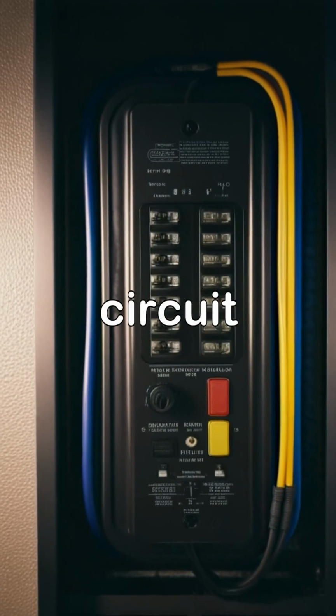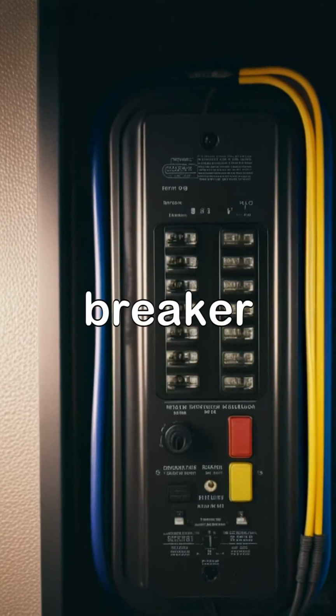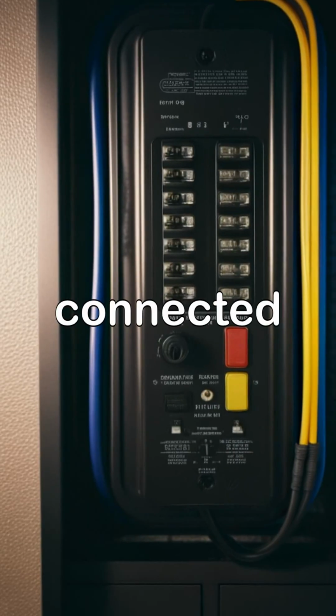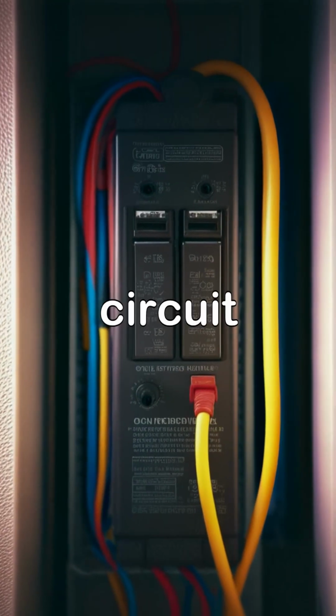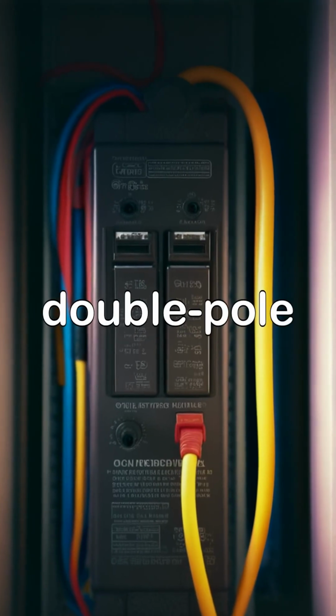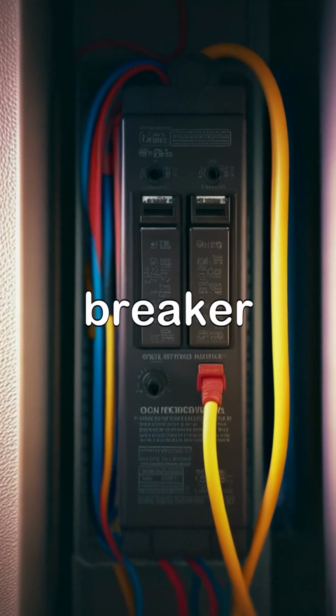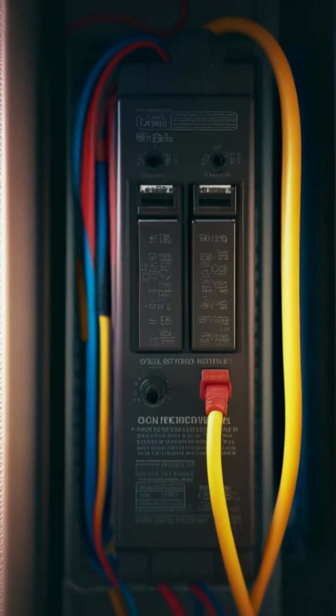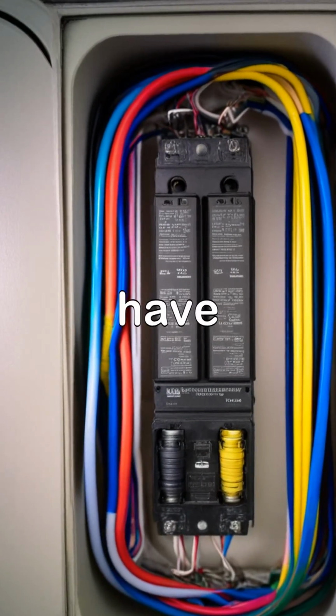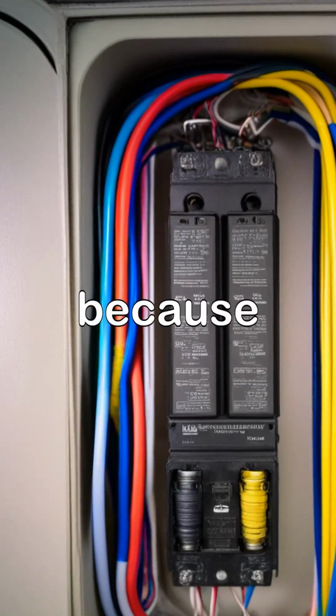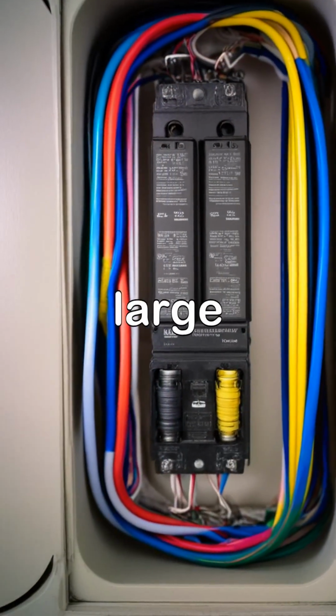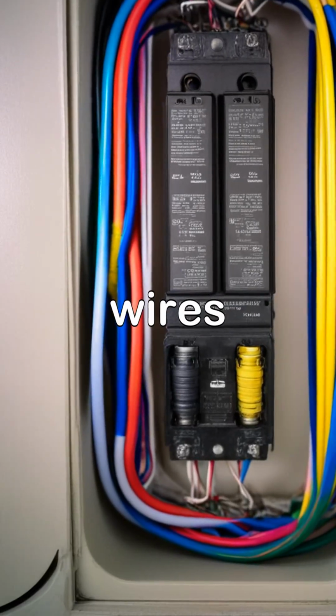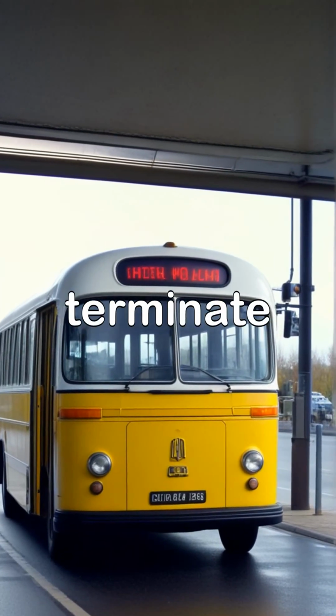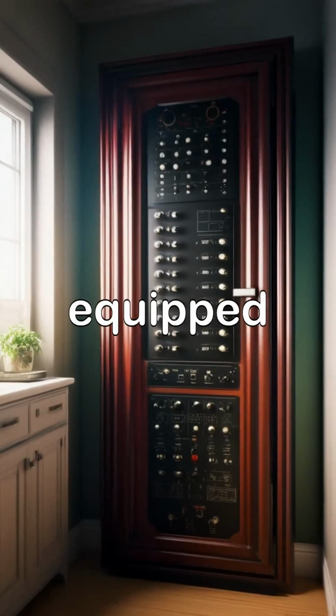A 120-volt circuit has 1 hot wire coming from a single-pole circuit breaker, that is, a circuit breaker connected to 1 hot bus bar, and a neutral wire or conductor that is connected to the neutral bus. A 240-volt circuit has 2 hot wires connected to a double-pole or 2-pole circuit breaker, that is, a circuit breaker that is connected to both hot bus bars. However, this 240-volt branch circuit may or may not have a neutral wire connected to the neutral bus. That's because 240-volt circuits for water heaters and large air conditioners do not require neutral wires. It is important to remember that all neutral conductors terminate at the neutral bus. Most homes are equipped with a variety of branch circuits.